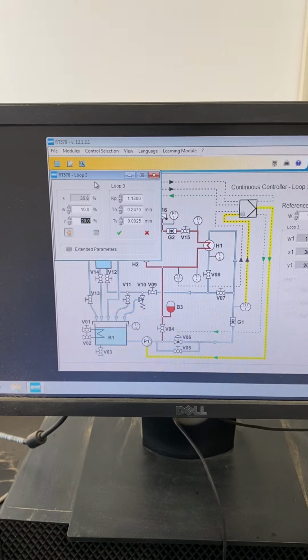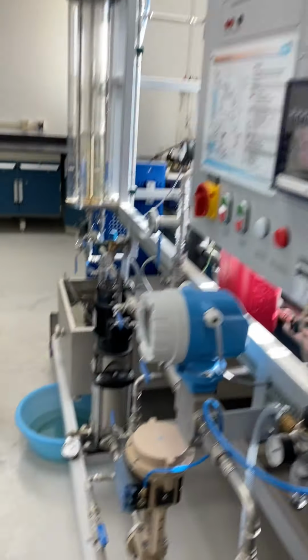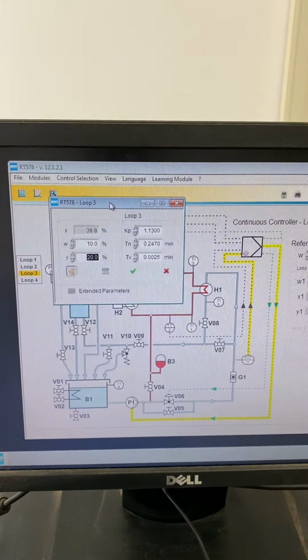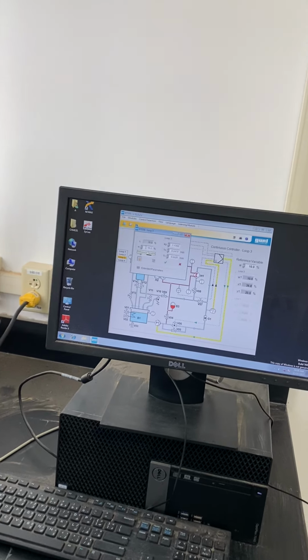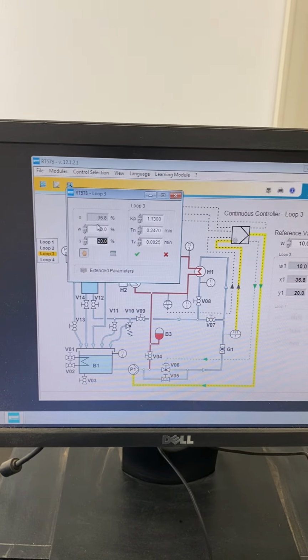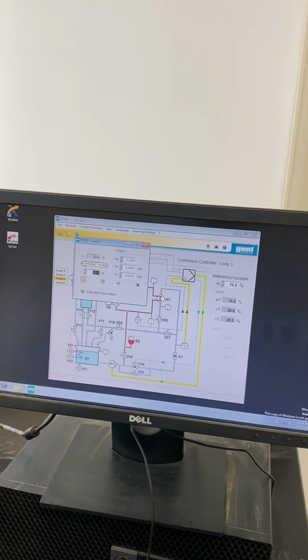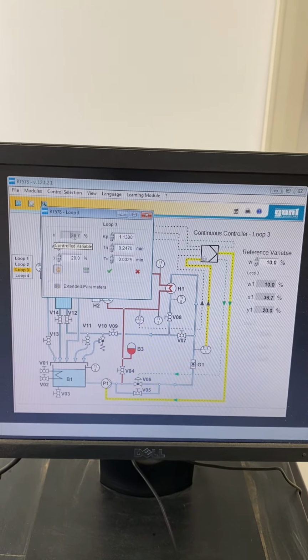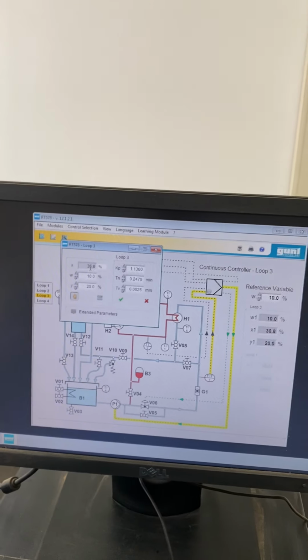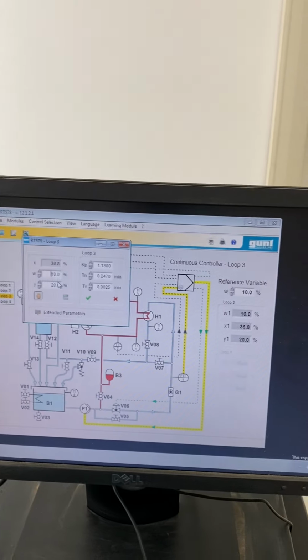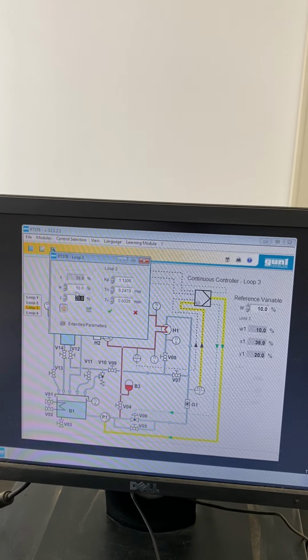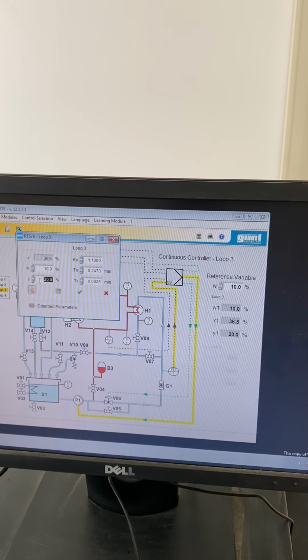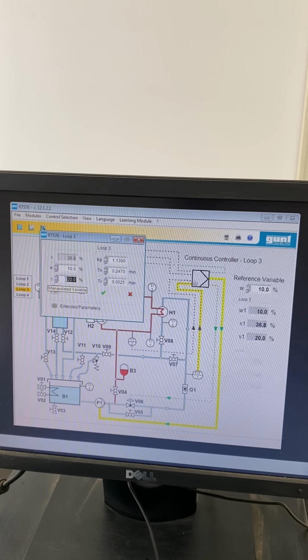Okay, so let me give you an example here. The system is operating right now. I'm controlling the process manually, and inshallah later on, when we follow the experimental procedure, we can switch to the automatic control. Now, I'm receiving a signal from the flow meter telling me that the current measured value of my control variable is around 36.8%. And the set point, guys, as you can see here, is around 10%. So I have to make the calculations. So there is about 26% error or difference. Based on that, I'm going to have to adjust the controller output signal.